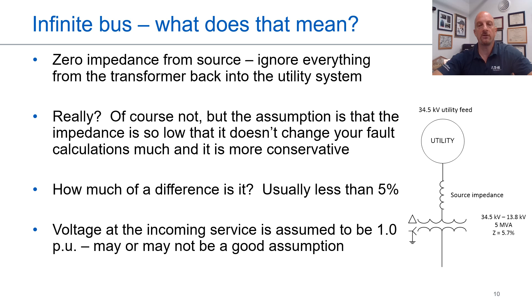So if we ignore that impedance, what are we doing? We're making the impedance lower. If the impedance is lower, our fault current is going to be higher. So it actually makes for a more conservative calculation. Now, what if our per unit voltage is not 480 or 13.8 kV, but maybe 5% high? Again, we have to think about that. So we may actually add a little bit of fault current into our final calculations.